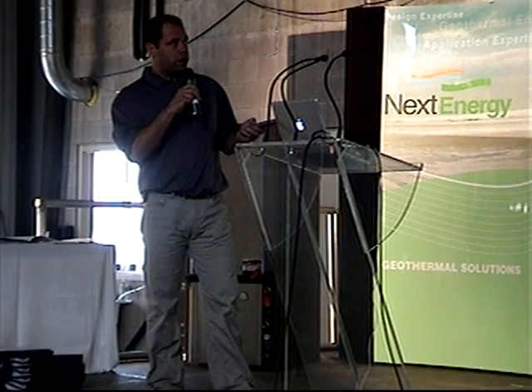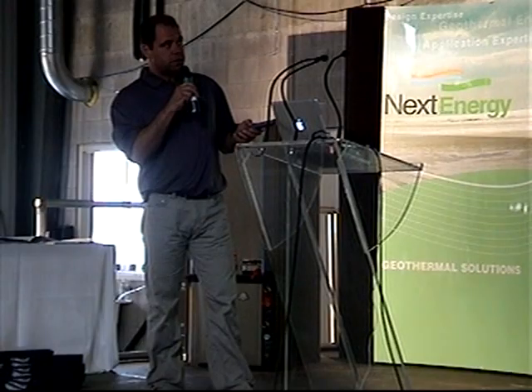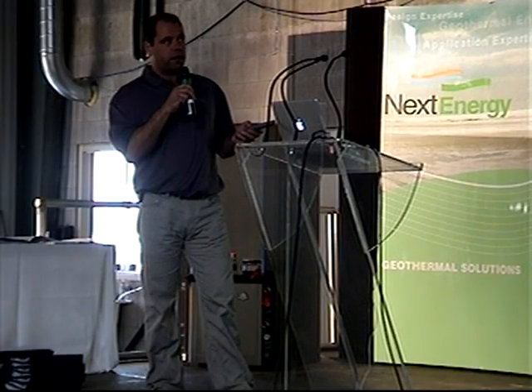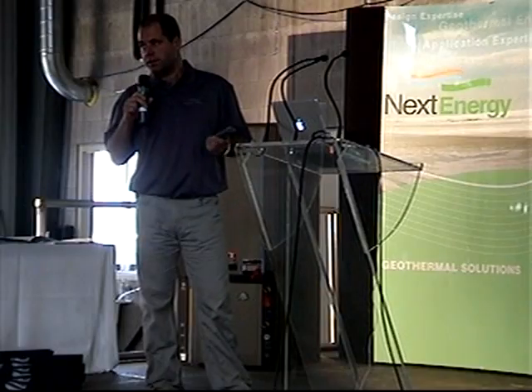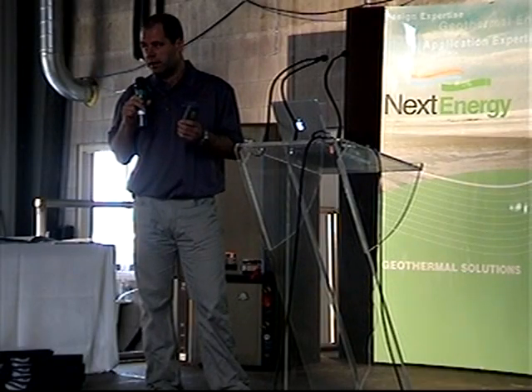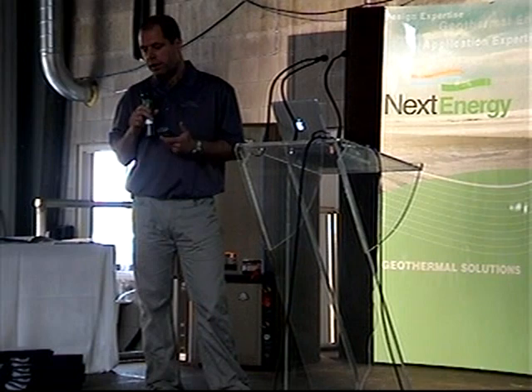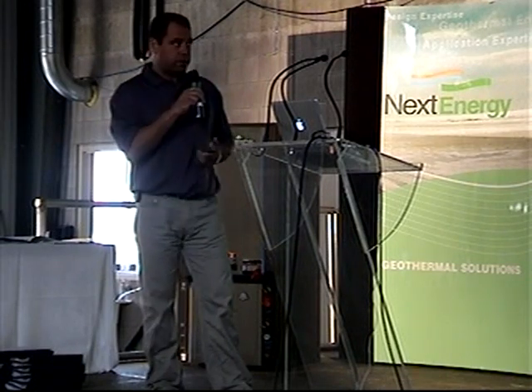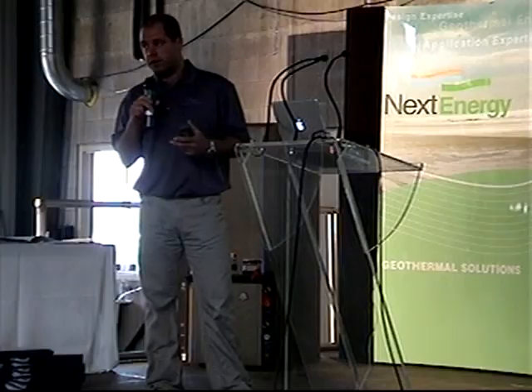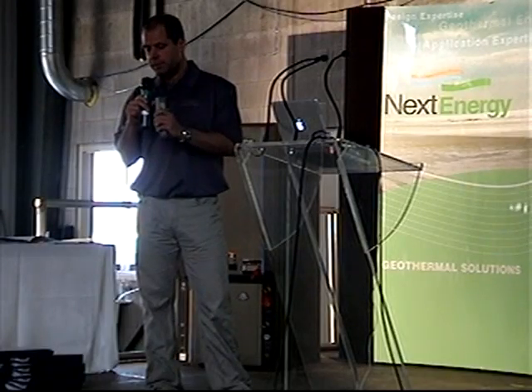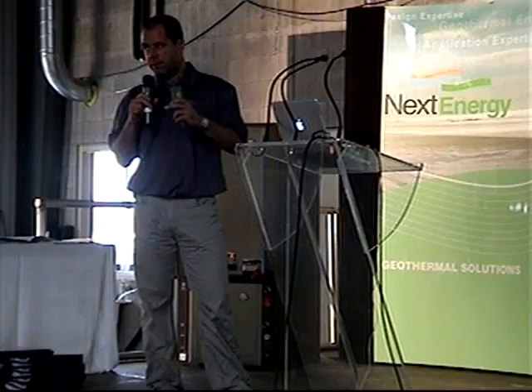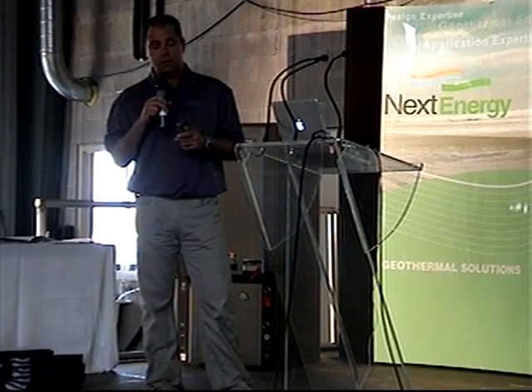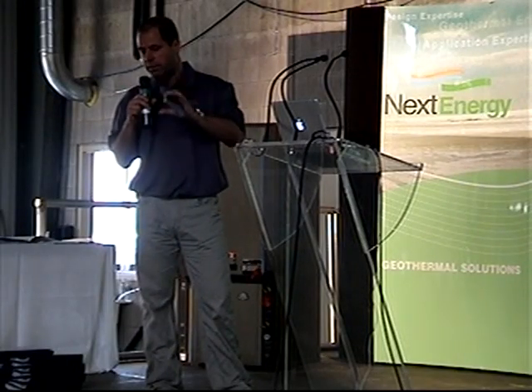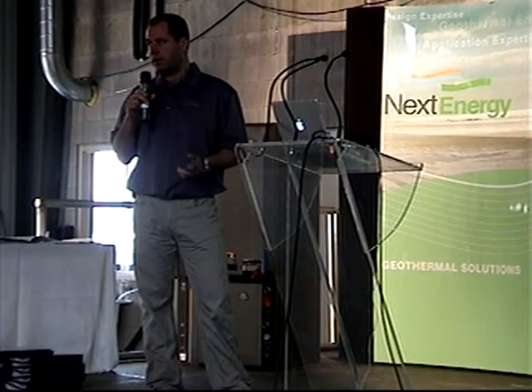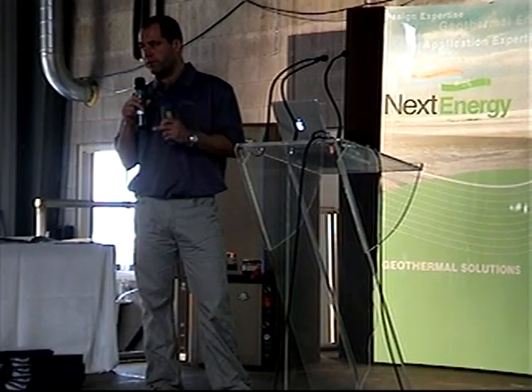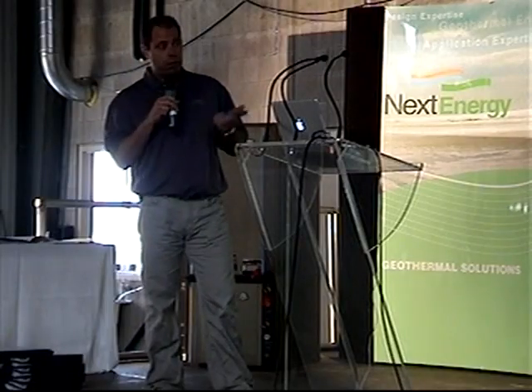So start off here, that's your suction temperature. You can measure that anywhere close to the compressor's fine. Just peel back a little bit of the insulation, put your sensor on, and we're also going to provide in the near future a thermometer. It's going to have six different ports on it. So you can hook it up to the unit while it's off, no power to it, stick your hands in there, mount all of your different sensors, turn the unit on, and one by one you can scroll through and get all your different temperatures, and you can do that while you're filling out this sheet.